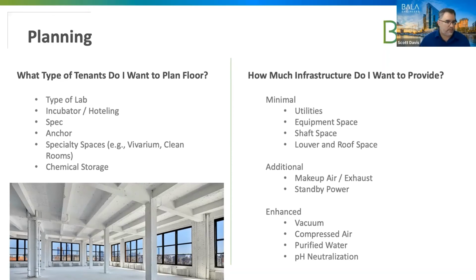The other things we look at are the types of utilities needed: equipment space, shaft space, louver, and roof space - really just looking at all the spatial requirements. As mentioned earlier, there's roughly a 6 to 8 square feet per floor requirement for shaft space, so you want to plan out how you're moving the ductwork up and down the building, assuming your supply and exhaust are separated, because there are code reasons the exhaust needs to be in a separate fire rated assembly or subduct configuration. Because it's deemed hazardous exhaust, you cannot put fire dampers in it. So there are situations you have to deal with that you wouldn't have in a typical office, because of the lab application.